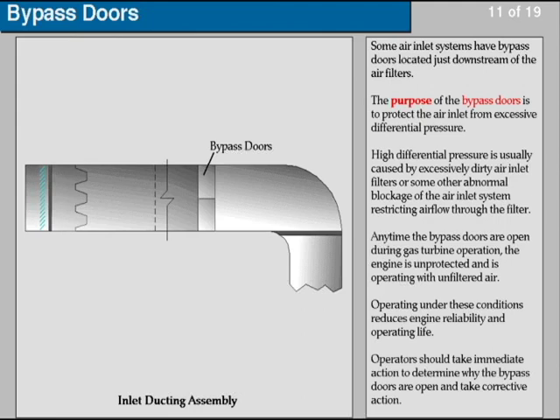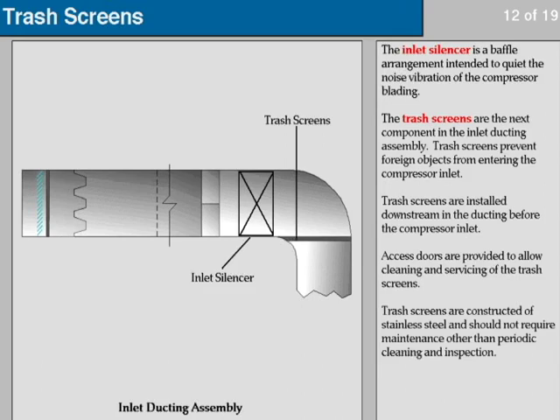Operating under these conditions reduces engine reliability and operating life. Operators should take immediate action to determine why the bypass doors are open and take corrective action. The inlet silencer is a baffle arrangement intended to quiet the noise vibration of the compressor blades. The trash screens are the next component in the inlet ducting assembly. Trash screens prevent foreign objects from entering the compressor inlet and are installed downstream in the ducting before the compressor inlet. Access doors are provided to allow cleaning and servicing of the trash screens.